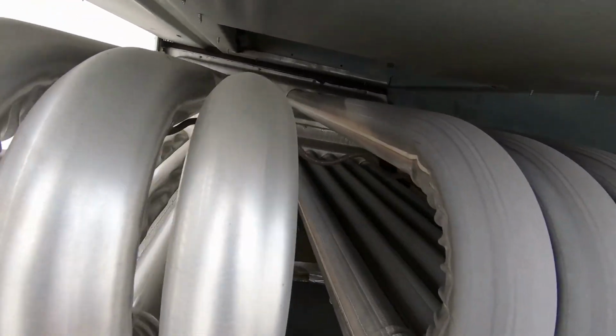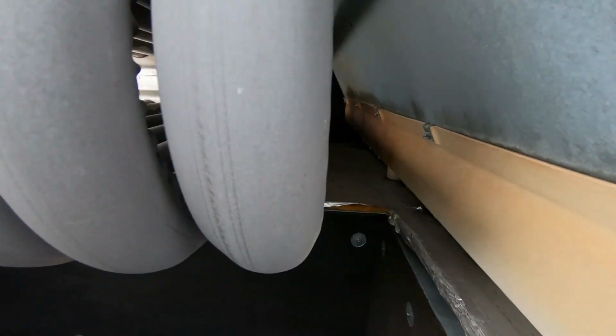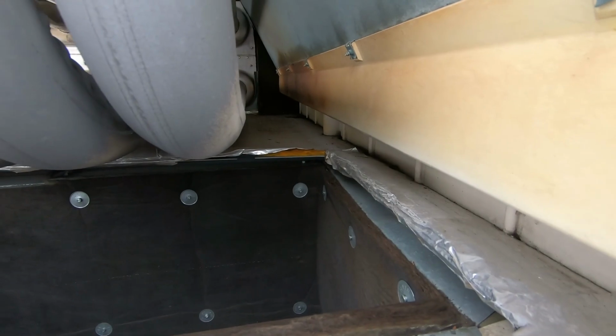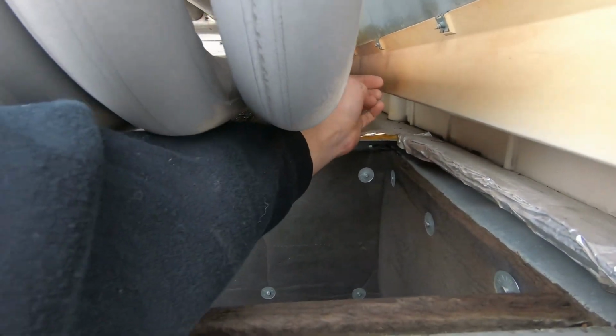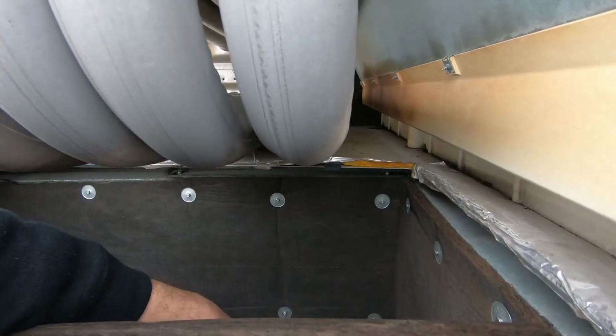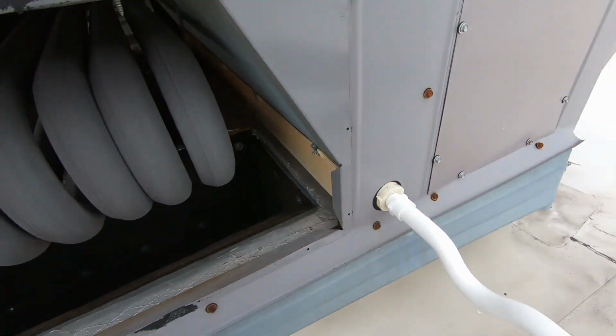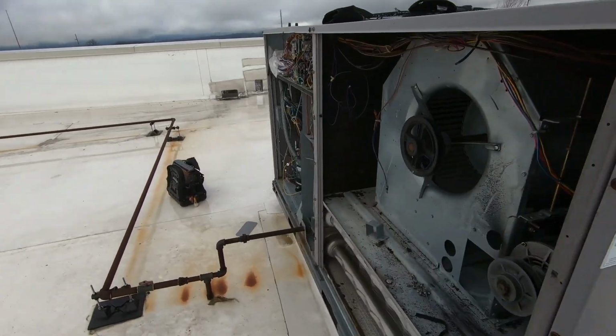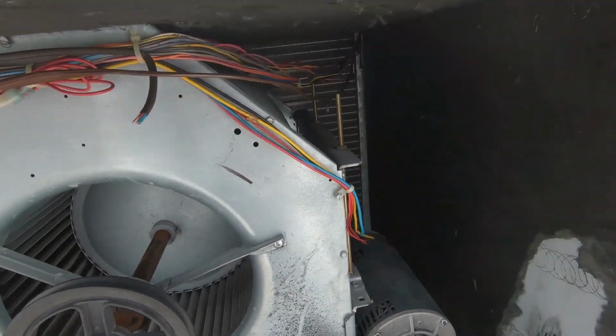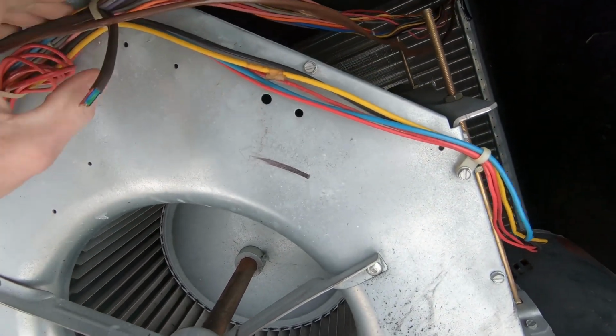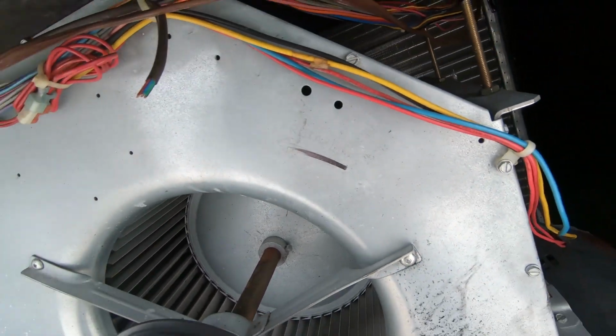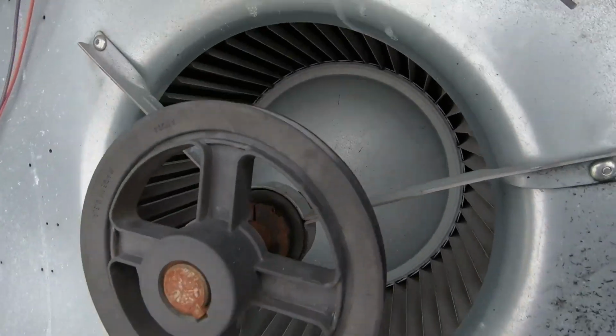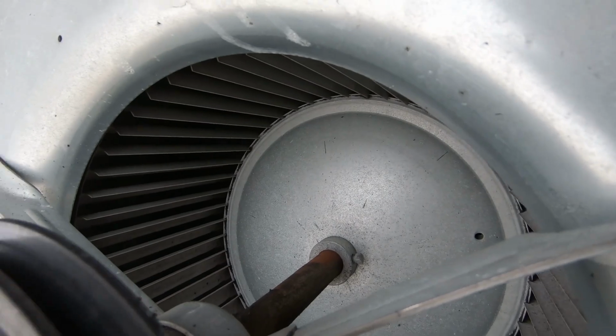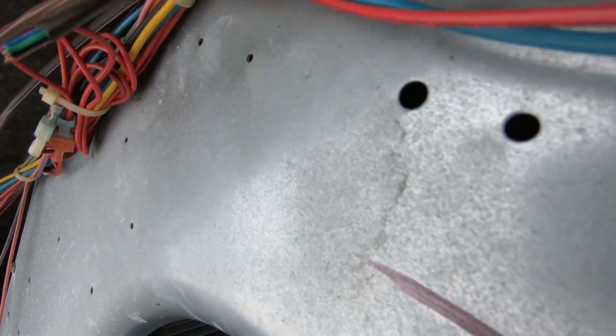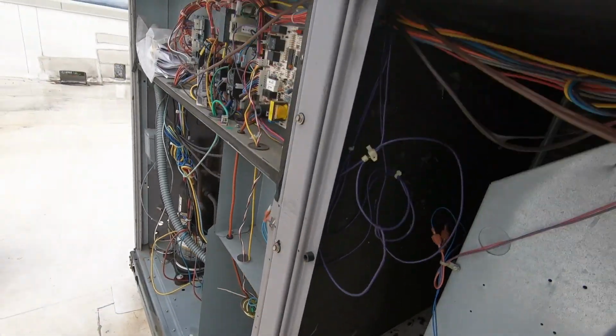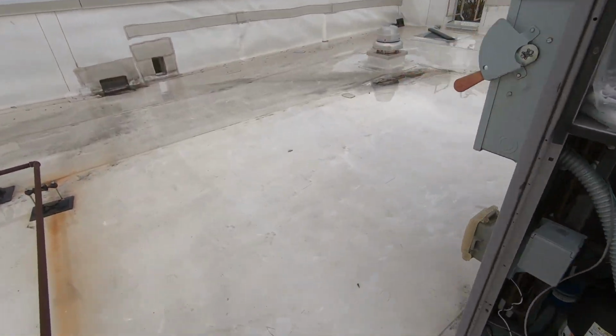Okay, it looks good. Looks like it did get hot, but yeah, that condensate pan up here looks like it had gotten pretty warm. So we're gonna leave all this open for now. I'm gonna check over all this wiring, make sure we don't have anything melted or rubbed out, but it stinks in this compartment. Oh yeah, look at that. Very, very close to being rubbed out. Let me cut that wire tie and get a closer look at all these wires.